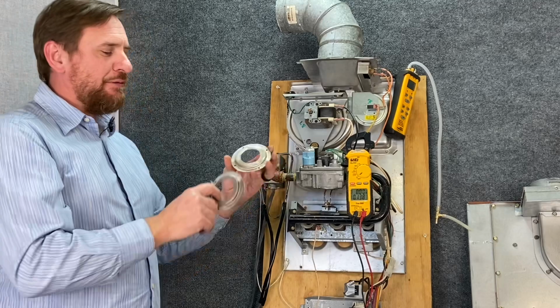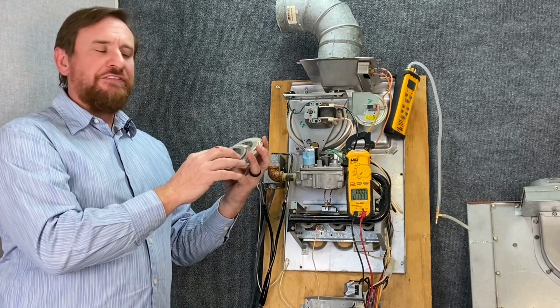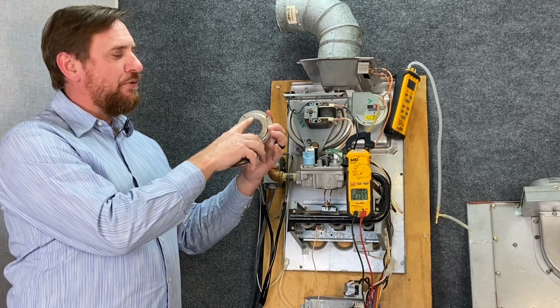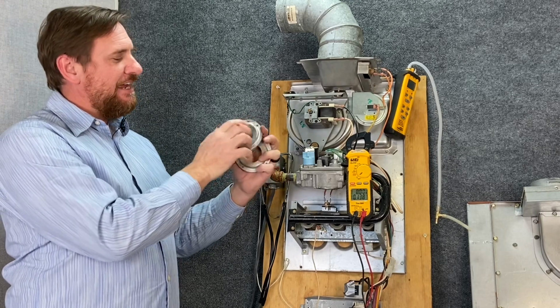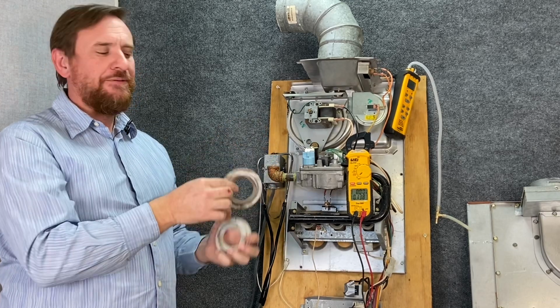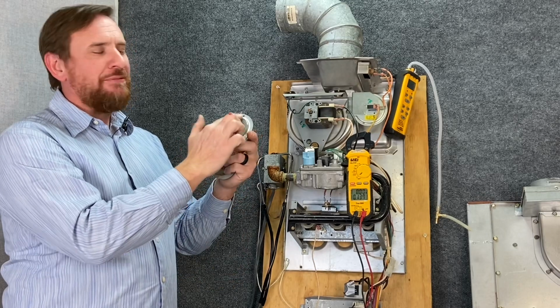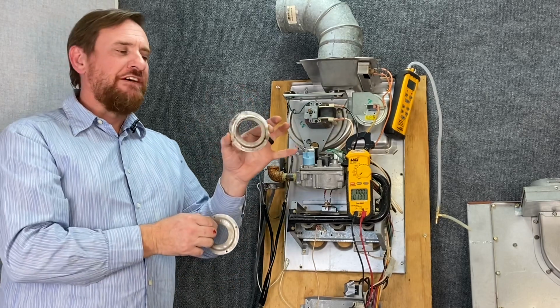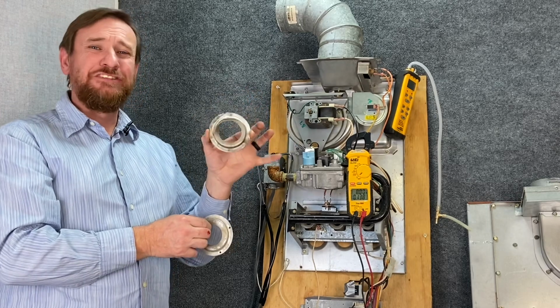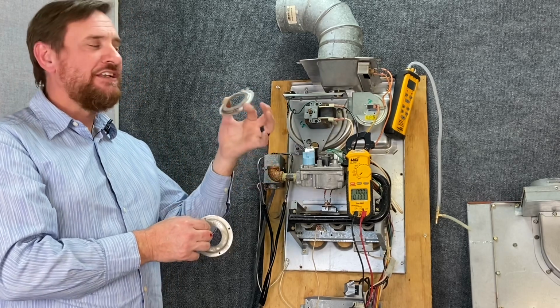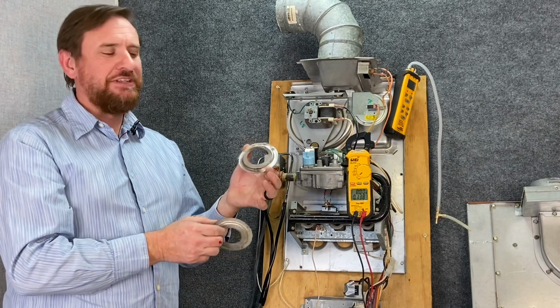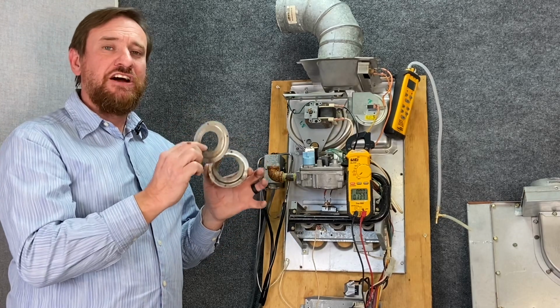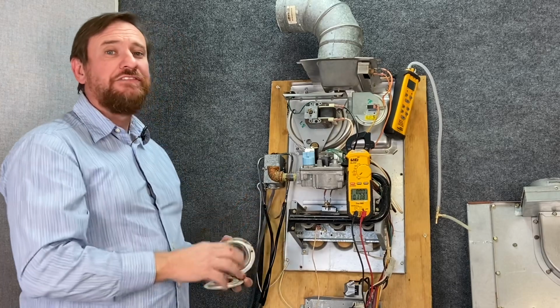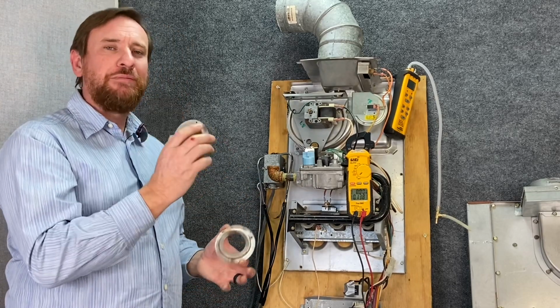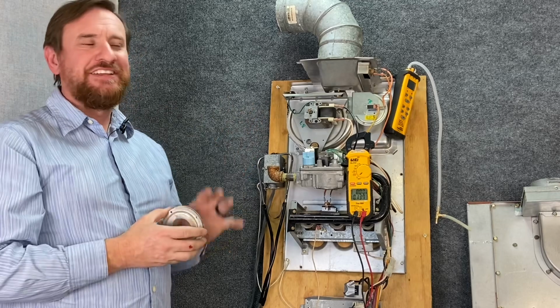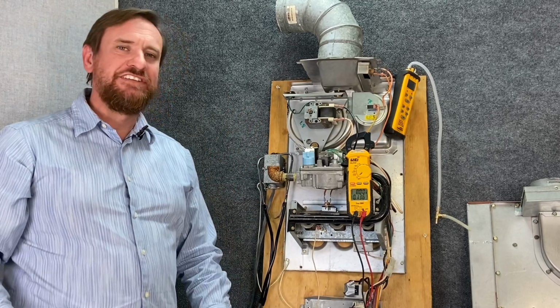Here's an example of some replaceable restrictor plates off of other units. This one's rated for 1.750 in size, and this one is a 1.938. This one has a significant amount of carbon built up on here because when we pulled this one off, we found that somebody put the wrong plate in its place. That caused incomplete combustion and caused the heat exchanger to die a short death. So if you ever pull this heat exchanger off or the inducer assembly off, you want to make sure you go back with the proper size restrictor plate because it can definitely affect the entire operation of these gas furnaces.